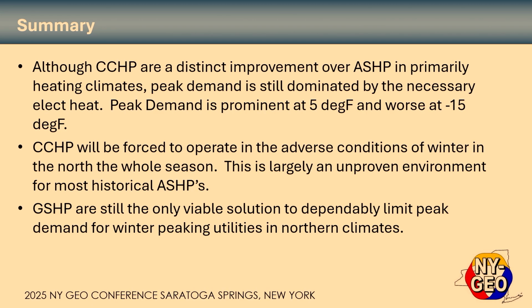So, although the cold climate heat pumps are a distinct improvement over the air source heat pump in primarily heating climates, the peak demand is still dominated by the necessary electric heat or gas, depending on how you're going to handle your decarb. And peak demand is prominent at 5 degrees, but much worse at minus 15. So the cold climate heat pump will be forced to operate in the adverse conditions of winter.